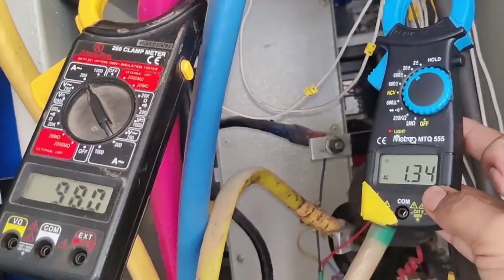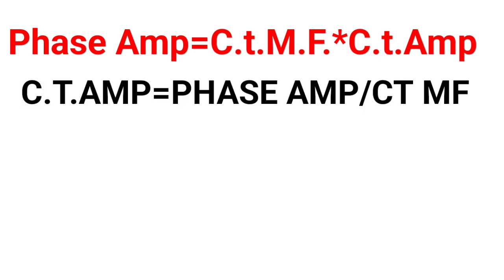We have two formulas to identify whether a CT is OK or defective. First formula: Phase ampere = CT multiplying factor × CT ampere. Second formula: CT ampere = Phase ampere ÷ CT multiplying factor. Using the first method, phase ampere = 80 × 1.34 = 107 amperes. But in actual, we find 98 amperes in R phase.